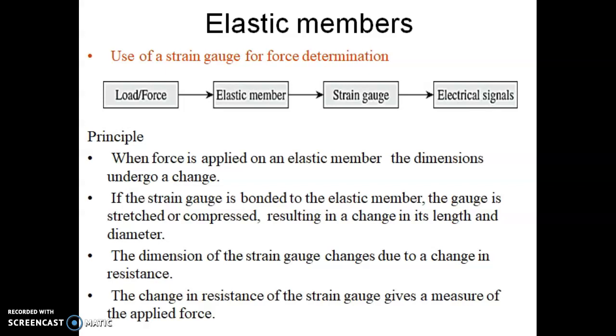Starting with elastic members or elastic transducers. The principle of elastic transducers is explained with the help of this picture. It contains an elastic member onto which a strain gauge is bonded. When a load or force is applied on the elastic member, it results in a dimensional change of the elastic member. This dimensional change changes the resistance of the strain gauge, and the change in resistance varies the potential difference or voltage, which is measured by an instrument.